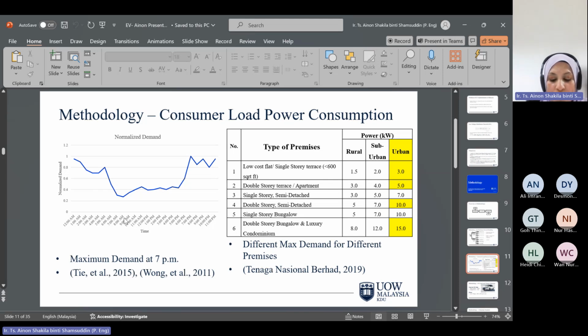So the actual demand in kilowatts can be determined by multiplying the maximum load demand by the normalized demand for the respective time slot. This table shows the data extracted from the TNB handbook. It shows that different types of premises will have different maximum diversity demand. The maximum diversity demand is for the urban area, whereby single story terrace, double story terrace, double story semi-detached, and also double story bungalow are used according to the number of types, as you can see from the table.